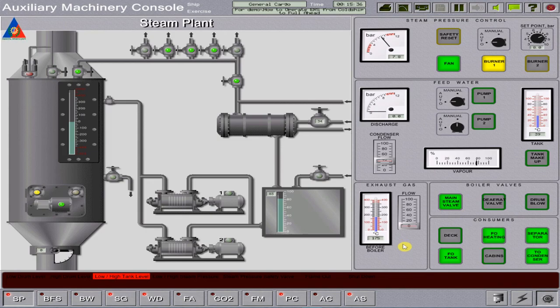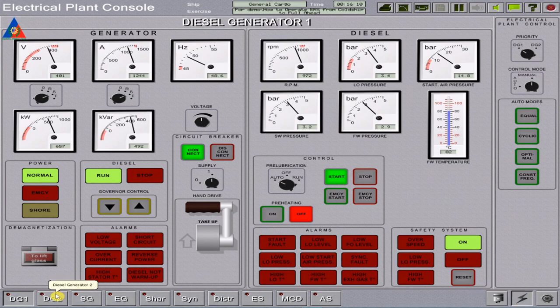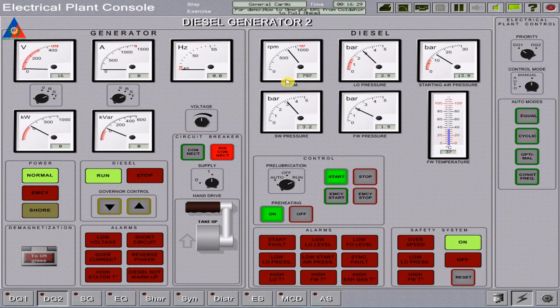Rectify the condenser tank high level alarm by running feed water pump number 1 and setting it to auto run mode. At the exhaust gas control panel, the combined boiler can use the power of the main engine's exhaust gases to produce steam. The flow of exhaust gases through the boiler is controlled with a butterfly valve; I have already opened the butterfly valve so that when we run the engine, exhaust gas will flow through the boiler. Proceed to the electrical plant console to start another diesel generator. Go to the DG2 page, run the pre-lubrication, press the preheating on button, and start diesel generator number 2.